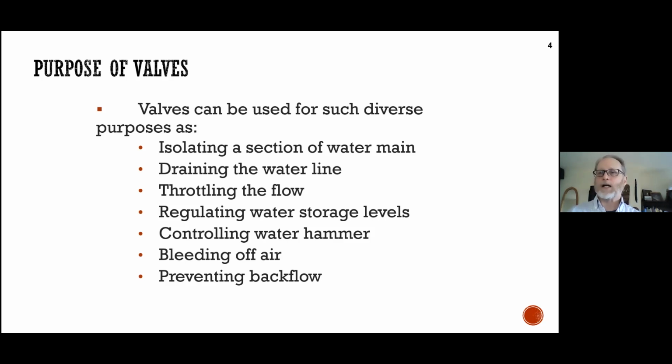We also have the ability to throttle, and throttle means we're not going to close the valve all the way down, right? The valve is going to remain partially open. Well, from our hydraulics, we know that when we change the cross-sectional area across a pipe by starting to close a valve, water tends to speed up and we get a pressure drop. And if you stood on the road or on the sidewalk where you have a valve and you have to isolate it because of a water main break, you can actually feel all of that turbulence as the velocity changes because you're slowly closing the valve. Well, if you don't close it all the way and it remains throttled, okay, we have reasons for doing that. It may seem like we don't, but you may be assigned to actually do that to prevent excess flow from moving from one area to the other.